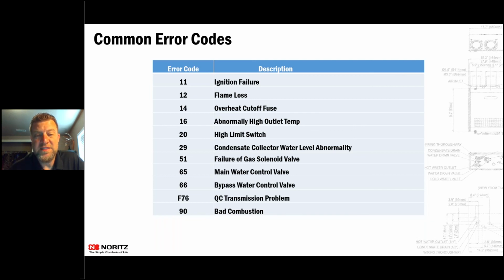So 14 and 16 kind of go hand in hand, because 14 is from some of the older technology units where we actually had an overheat cutoff fuse that was wrapped around the heat exchanger. If that heat exchanger got too hot, it would burn that fuse and separate it, and you'd get a 14 code. With the newer units, it is a resettable thermal switch on the top of the unit. So if that heat exchanger gets too hot, it will flash a 16 code, or in the older units a 14 code. Biggest contributor to this is scale buildup inside of that unit.